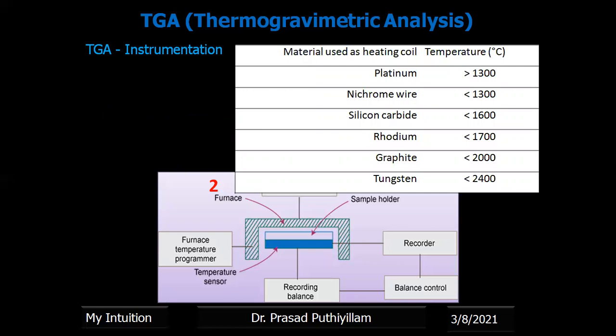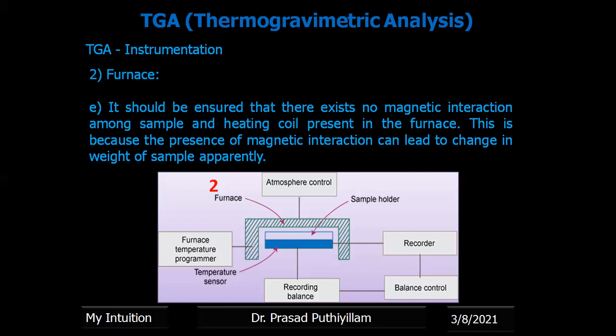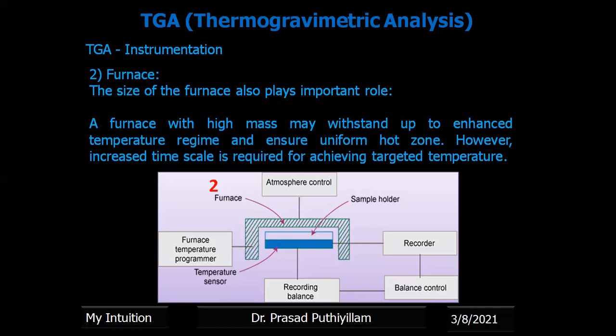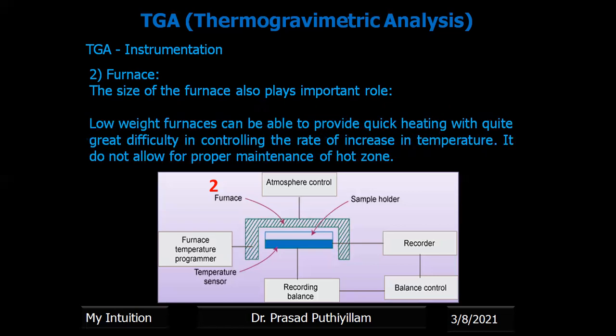Tungsten is used when the temperature conditions required are below 2400 degrees Celsius. The heating coil used should not create any magnetic field, as a magnetic field will affect the change in mass of the sample. The size of the furnace also plays an important role. A furnace with high mass will ensure a uniform hot zone but takes more time to reach the required temperature. Whereas low-weight furnaces result in quick heating but difficulty in controlling the rate of temperature increase.